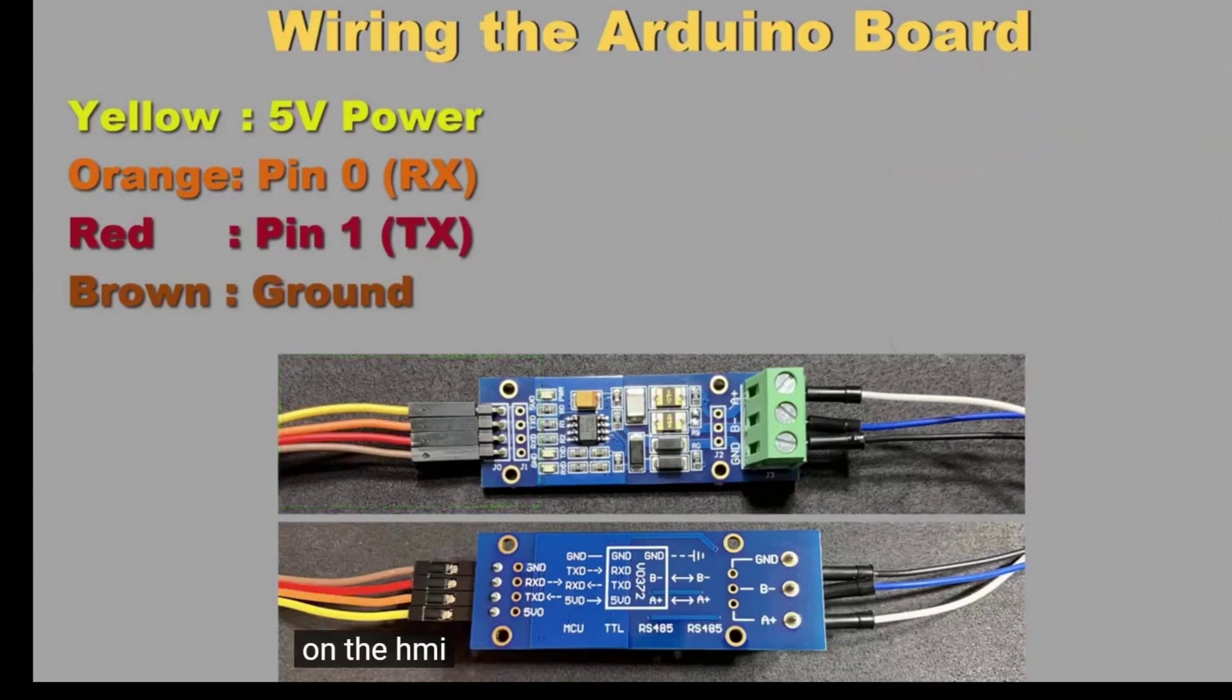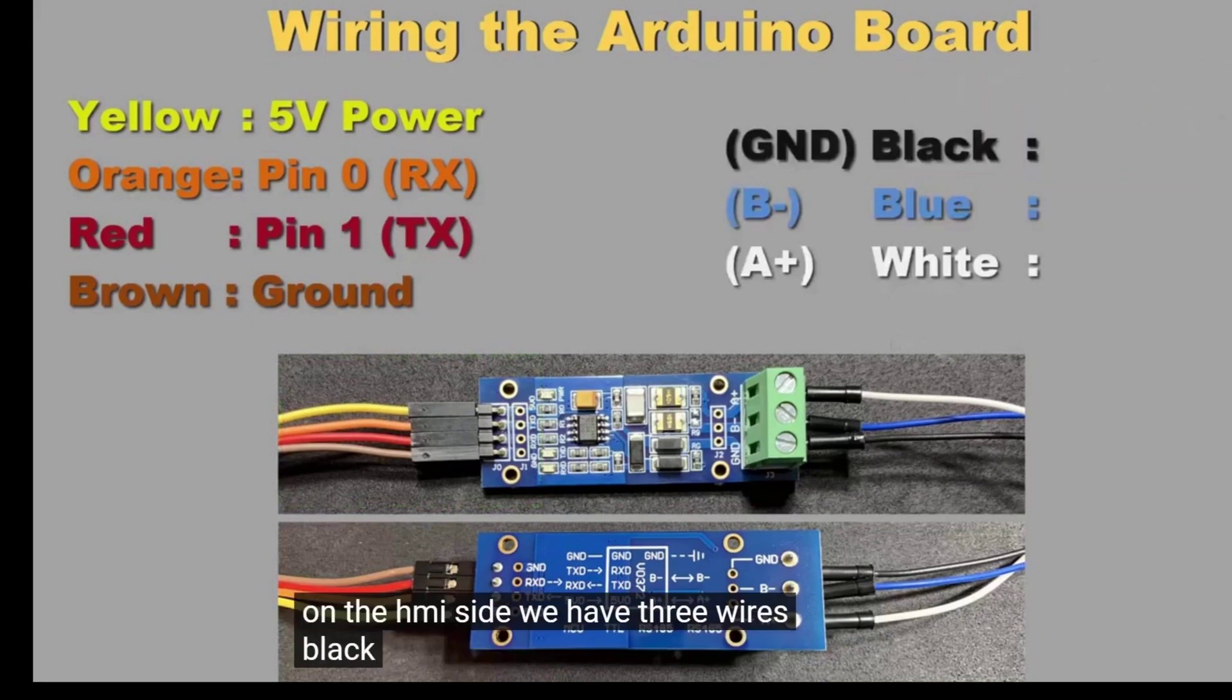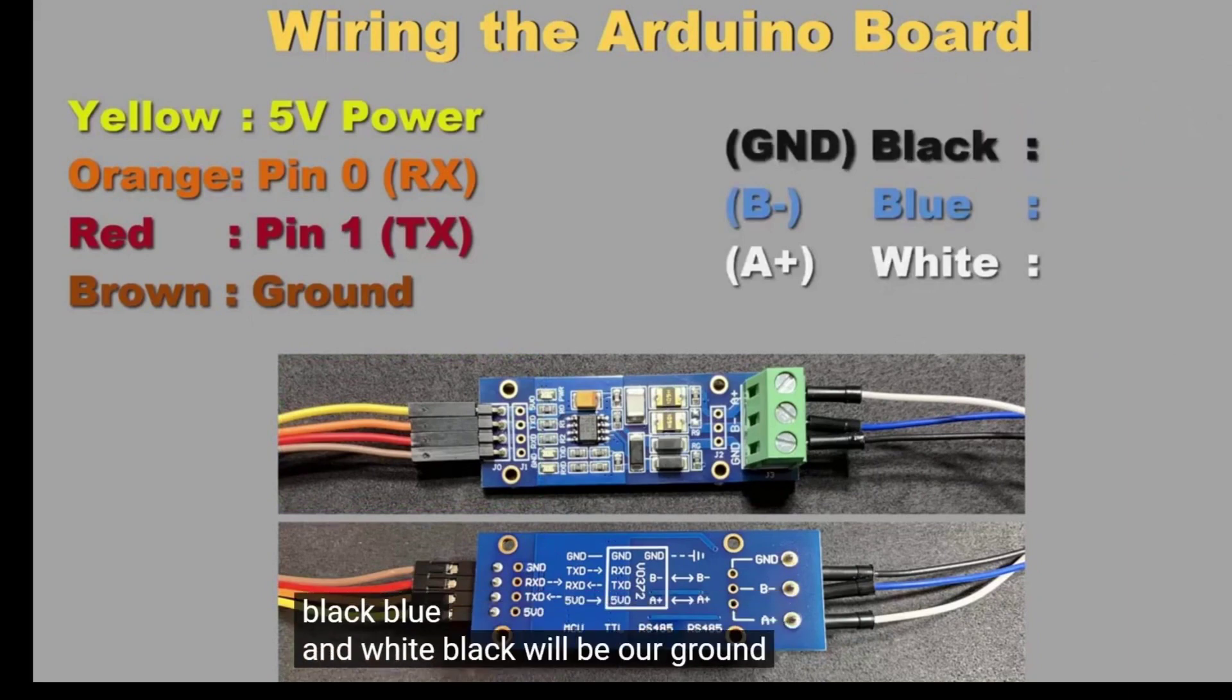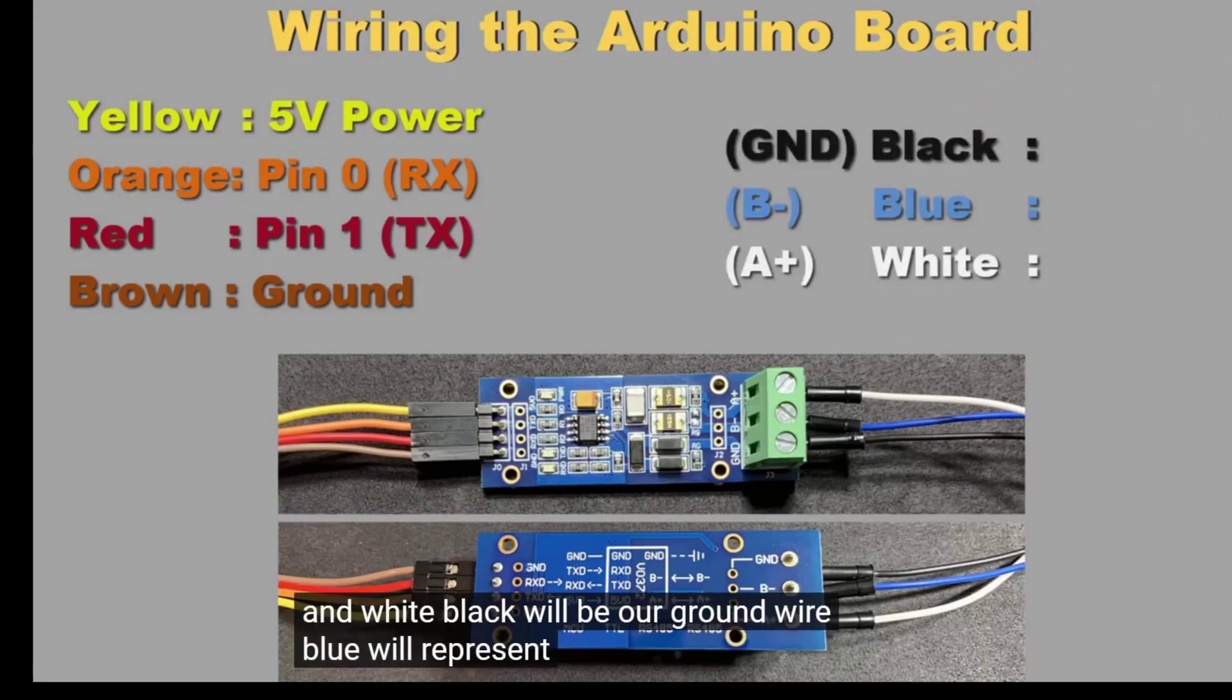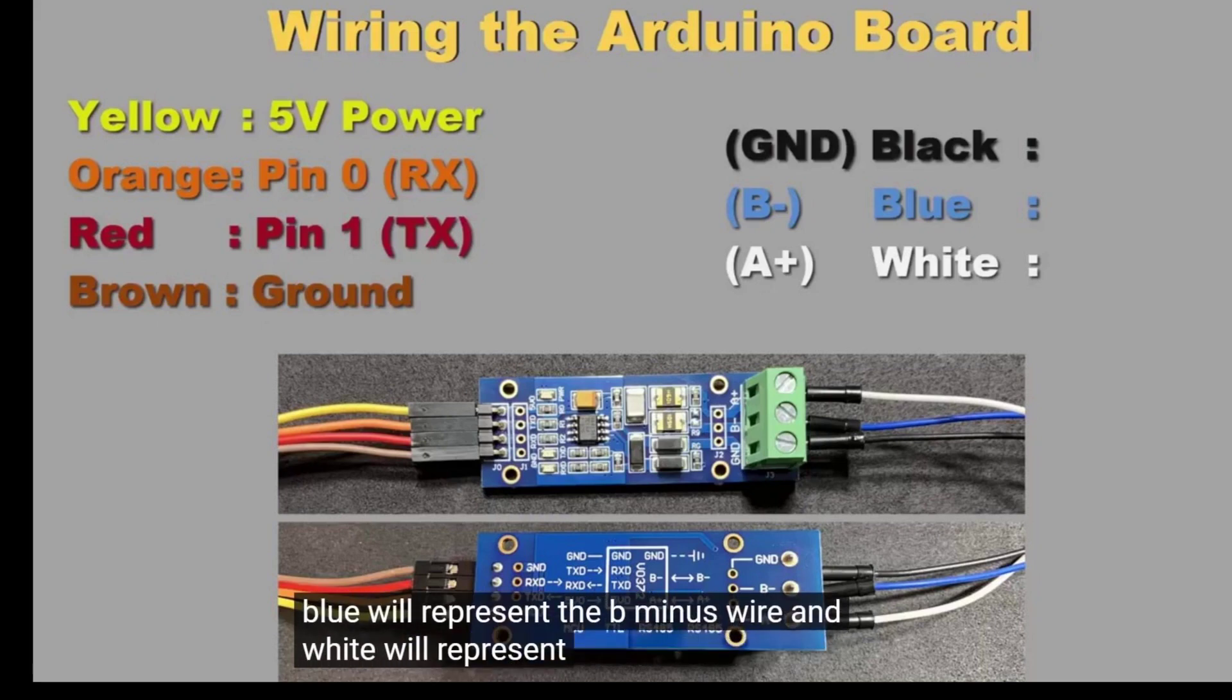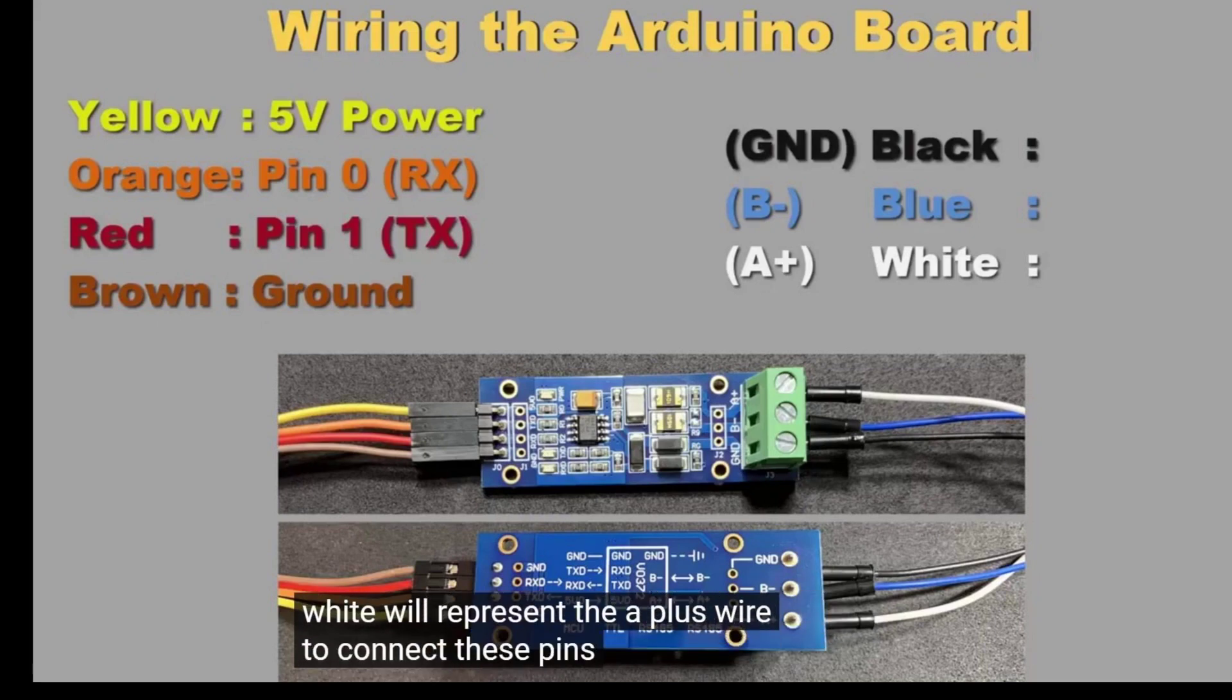On the HMI side, we have 3 wires: black, blue, and white. Black will be our ground wire. Blue will represent the B-minus wire, and white will represent the A-plus wire. To connect these pins to our HMI, I will be using a serial communication adapter.